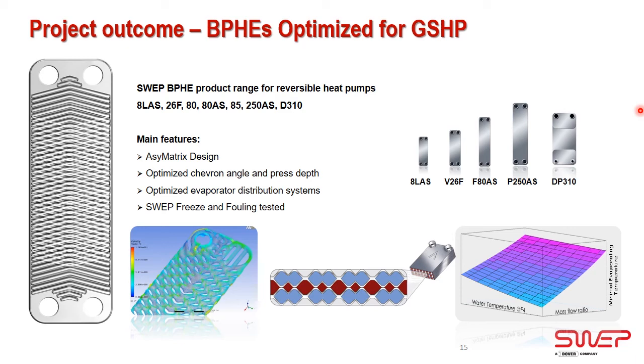SWEP has over 35 different brazed plate heat exchanger models. For reversible heat pumps, we now have a complete range from less than 1 ton up to more than 30 tons of reversible duty, with the 8 LAS, 26 ADAS, etc. Some of them are symmetric, some of them are asymmetric, depending on the requirements of the application. We have single circuit with one refrigerant circuit and one water circuit. We have dual circuits with 2 refrigerant circuits and 1 water circuit, using different refrigerant systems.